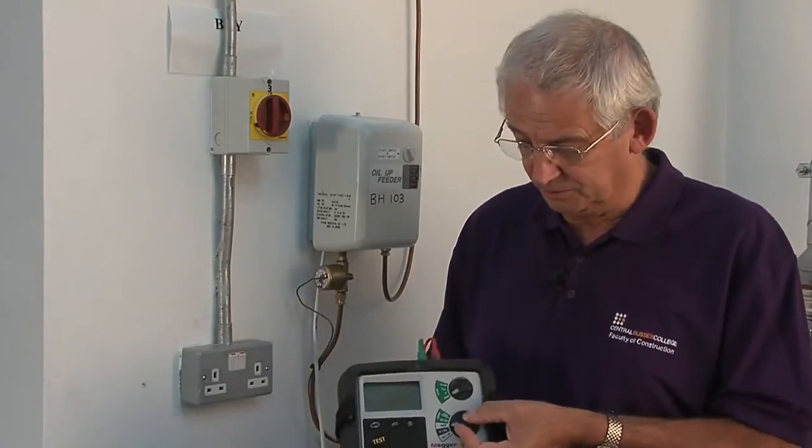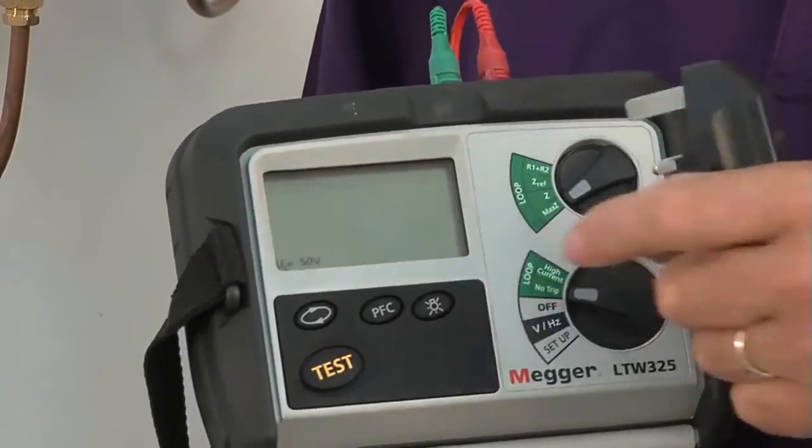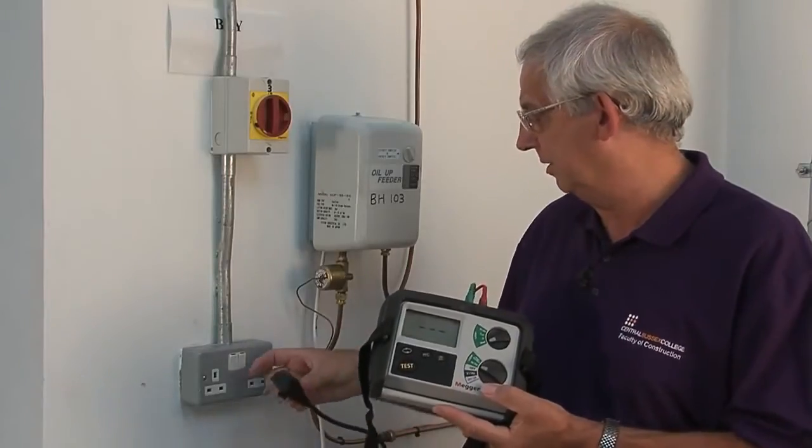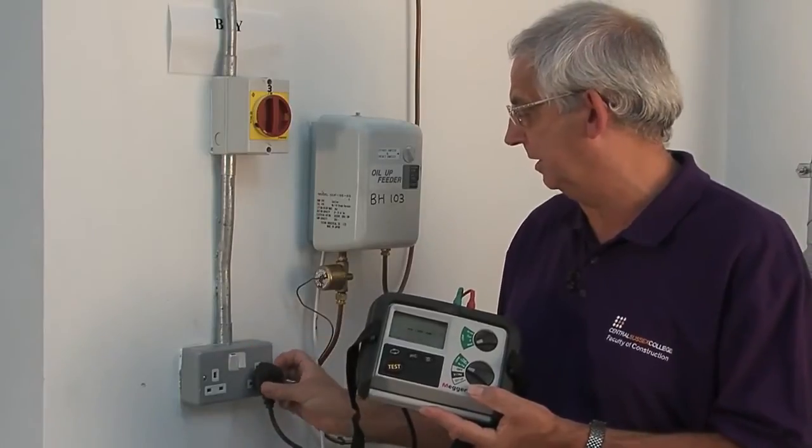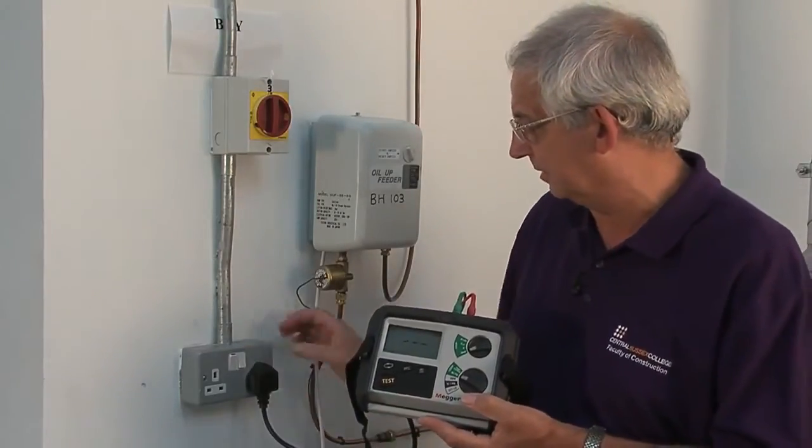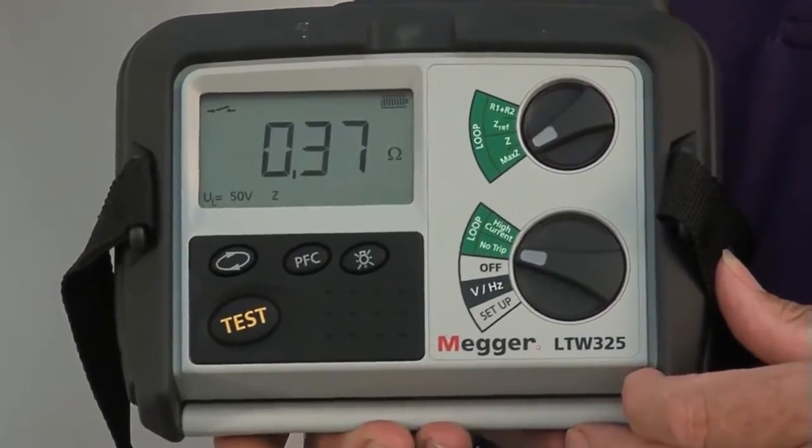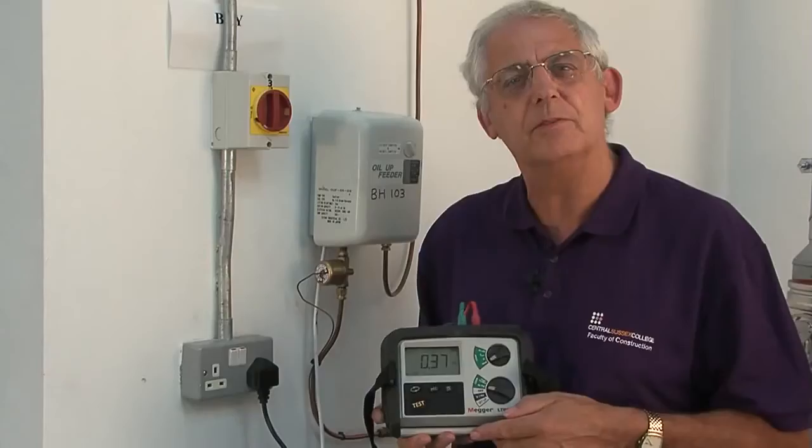This is one of those instruments, so I set it to no trip. And then all I need to do is a very simple procedure: plug the instrument into the socket, switch it on. Now I've got the result, which is 0.37 of an ohm.